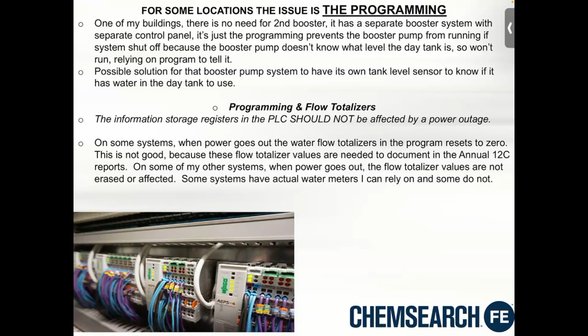On some of my systems, when the power goes out, the flow totalizer values are not erased or affected. So they should all be like that. So it's just a programming issue. I do have some systems where, when the flow totalizers zero out, I just have to rely on the water meters. But some of my buildings don't have water meters where I need to keep track. So that's something that should be standardized: it doesn't lose the data inside the PLC when power is lost.